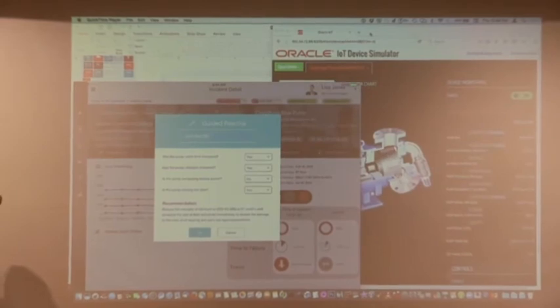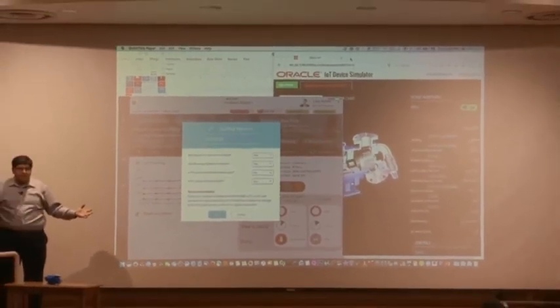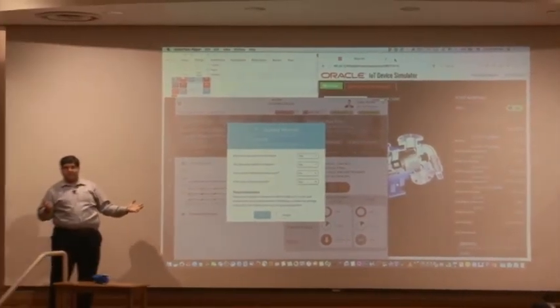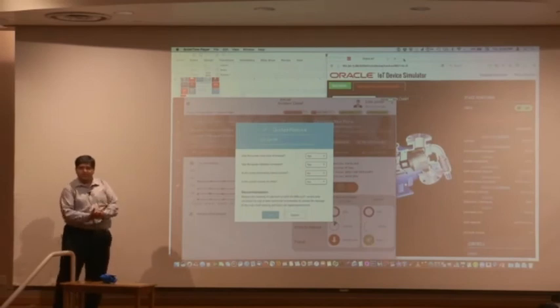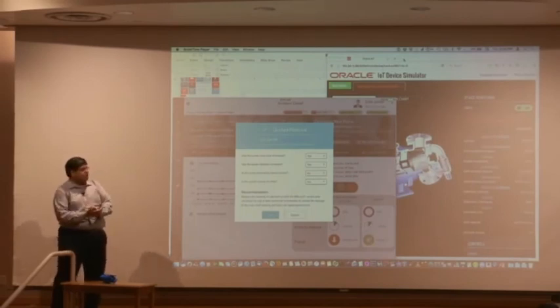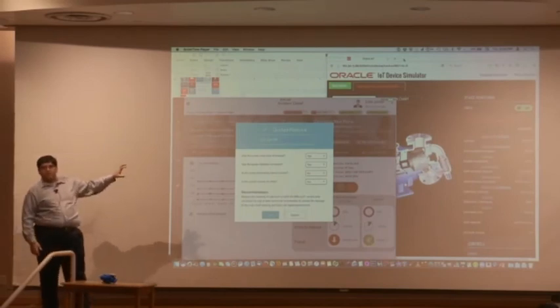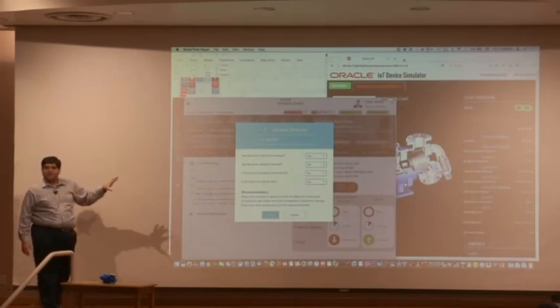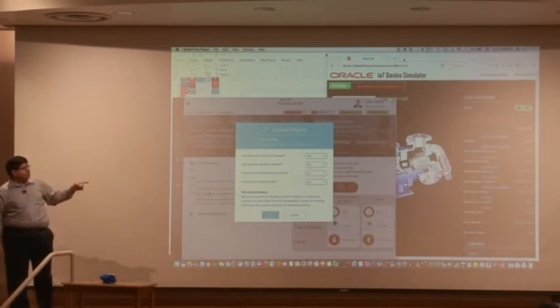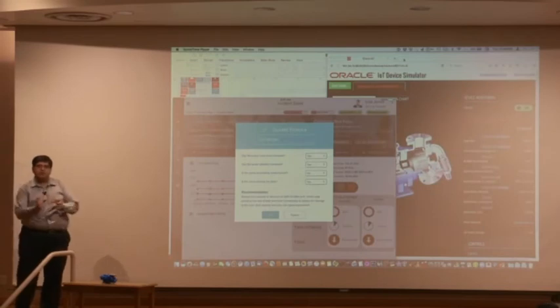In a normal circumstance, what would you think? There's an issue with the bearing, it's become red - what would be the first reaction? Reduce the pump operation, right? You'd reduce the frequency of the pump. But on the contrary, according to the service manuals provided by the pump manufacturer, reducing the pump frequency is going to cause the vibration to increase and cause the pump to fail almost immediately.